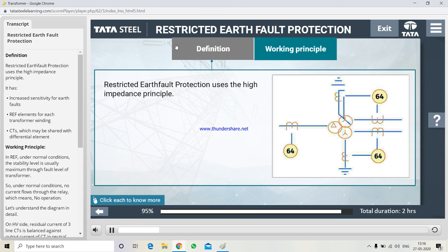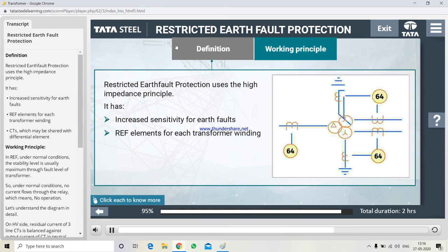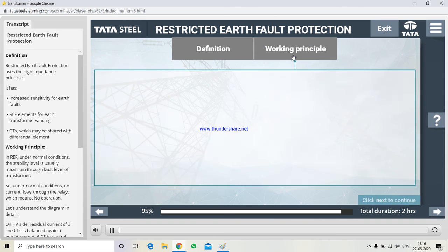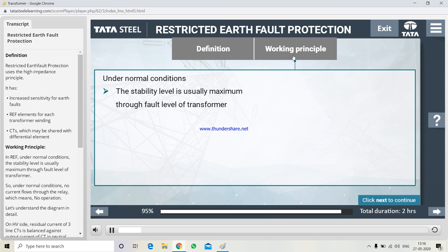Restricted earth fault protection uses the high impedance principle. It has increased sensitivity for earth faults, REF elements for each transformer winding, and CTs which may be shared with the differential element. In REF, under normal conditions, the stability level is usually maximum through fault level of the transformer. So, under normal conditions, no current flows through the relay, which means no operation.